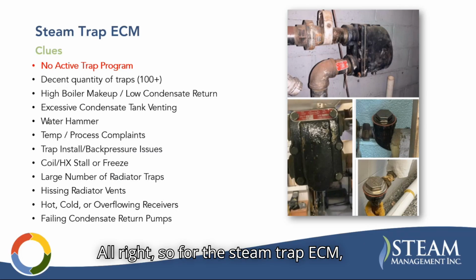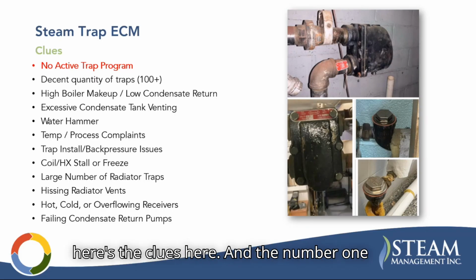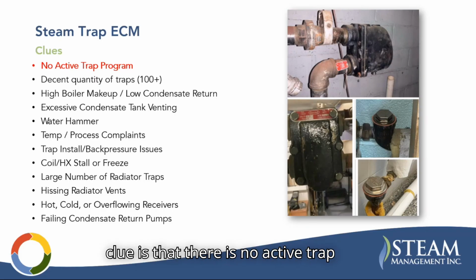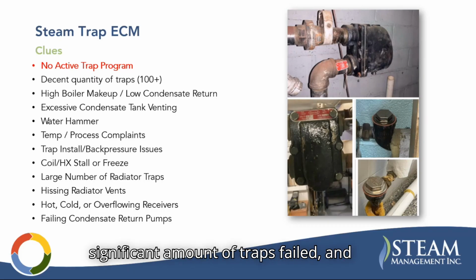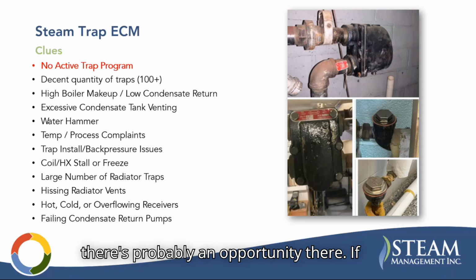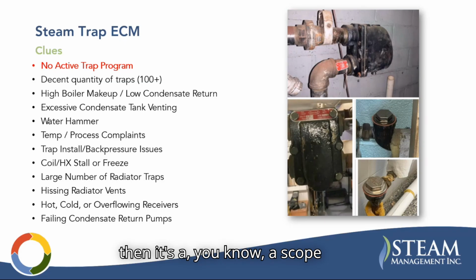All right, so for the steam trap ECM, here are the clues. The number one clue is that there is no active trap maintenance program. Traps fail every year. Like I mentioned, you're going to lose 5 to 10% of your traps every year. If they're not maintaining their traps every year or every 2 years, there's going to be a significant amount of failed traps, and there's probably an opportunity there. If they have a decent quantity of traps, then it's a scope worth looking at. And all these other things are indicators as well.